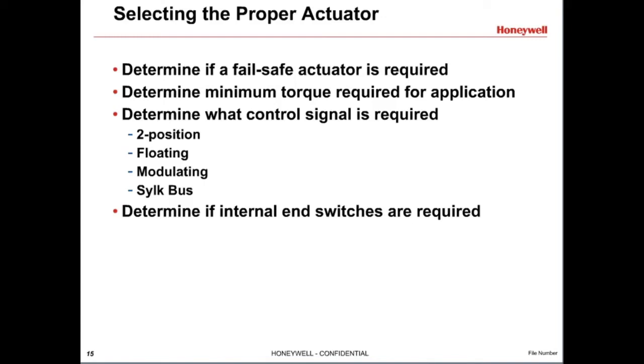The control signal is another important factor. Two-position control, also called on-off or open-closed, is a simple on-off control signal where the actuator will drive one direction when the power is applied, then it will spring return when power is removed. Modulating control can be either floating or proportional control. Floating control is also called tri-state or 3-point. It sends the actuator a signal to drive one direction for a set amount of time, and another signal to drive the actuator in the other direction.